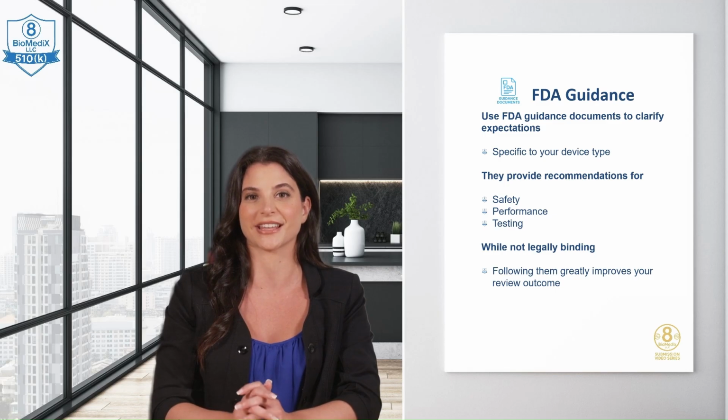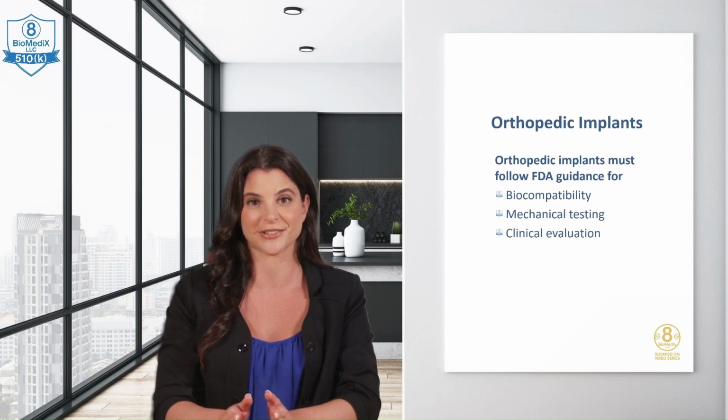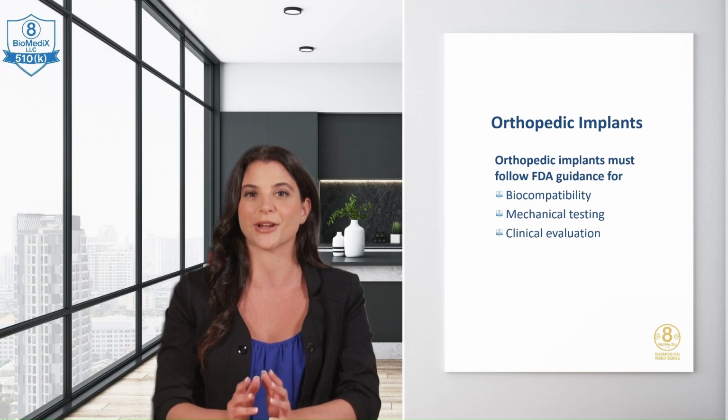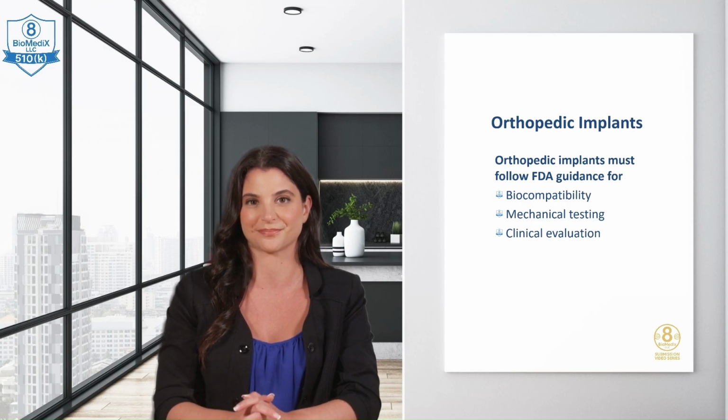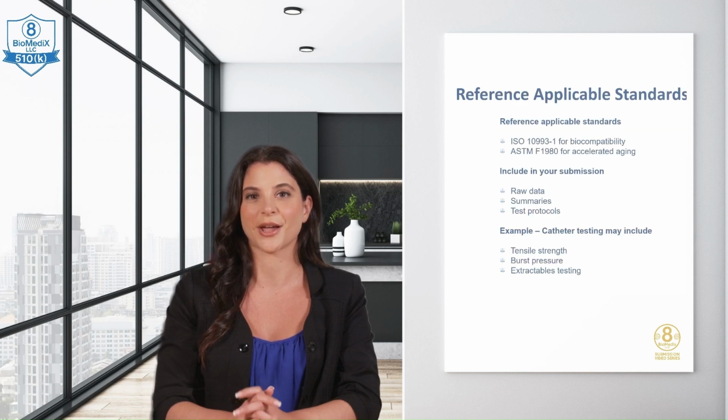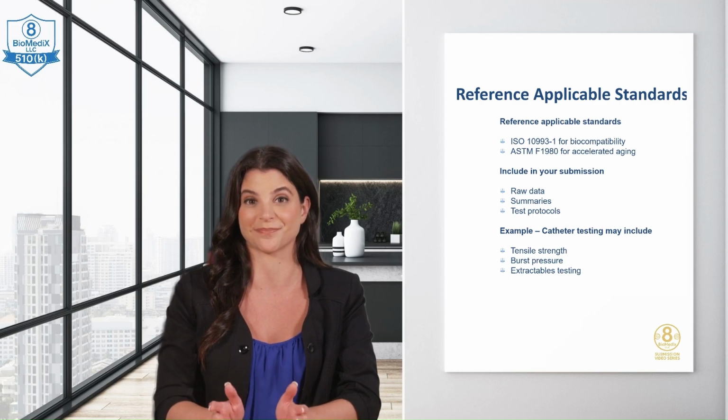Also, use FDA guidance documents to understand expectations for your device type. These provide recommendations for safety, performance, and testing. While not legally binding, following them improves your review outcome. For instance, orthopedic implants must follow FDA guidance on biocompatibility, mechanical testing, and clinical evaluation.